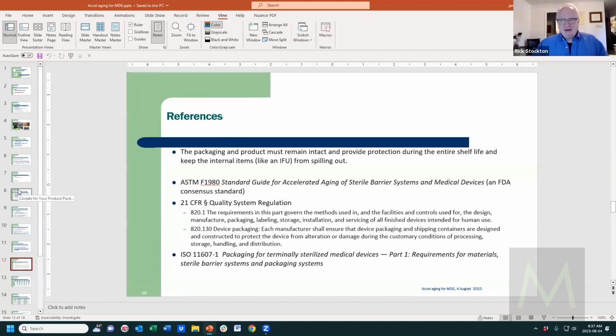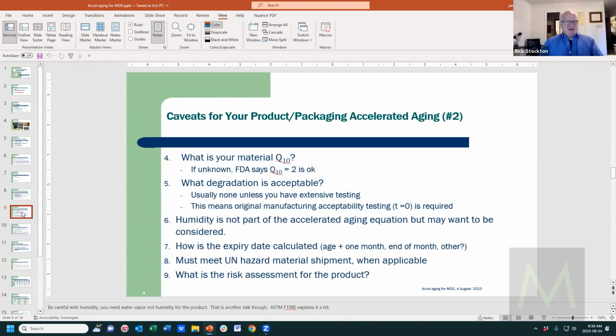Oh, actually, I've got a question. So I've been involved in projects that had accelerated aging. In one instance, the accelerated aging was so extreme that it actually melted some of the internal components. But we did a great job designing it, so it still worked. But my question is this: there's always the question of how well the accelerated aging represents actual true aging, and I'm wondering, is there a number for it or a factor or something like that? In other words, if we do some scheme of accelerated aging and we say we're 90% sure that this is going to represent 2 years in storage at whatever, is there a degree of certainty that is used to rate different accelerated aging protocols?